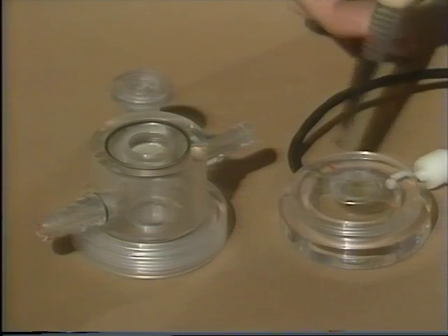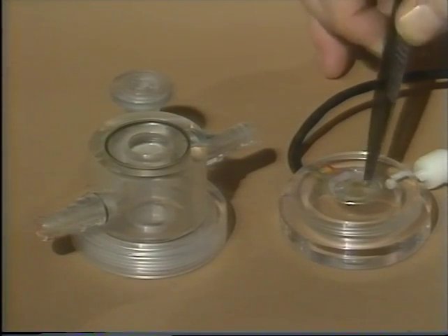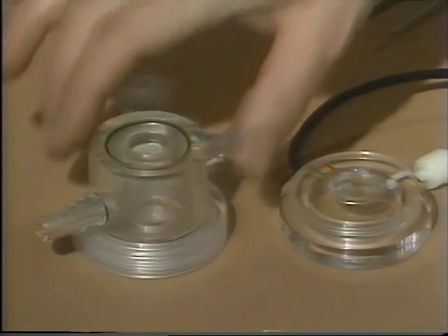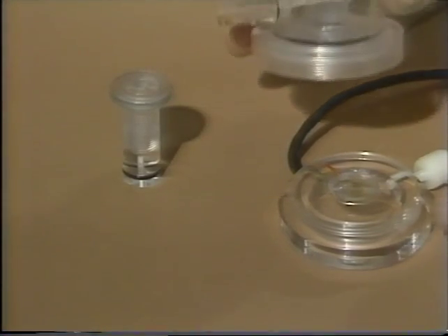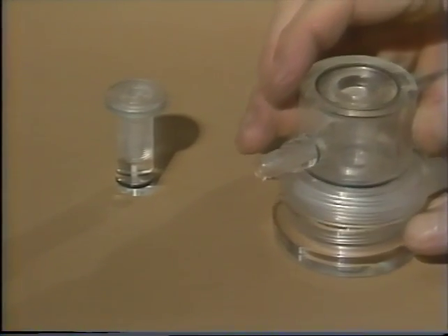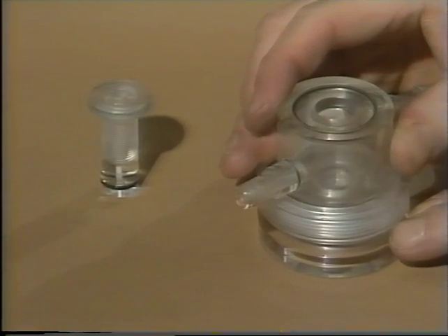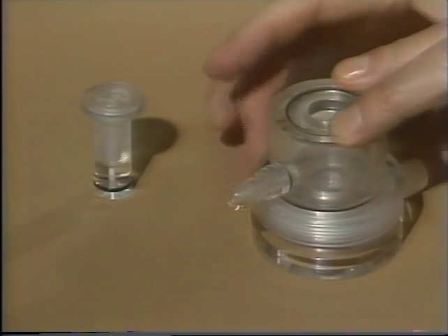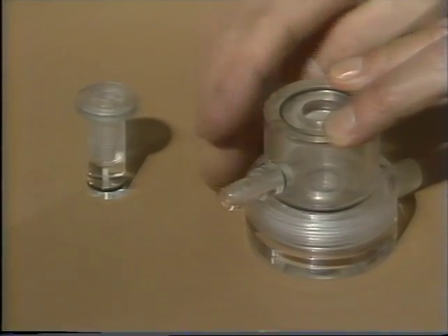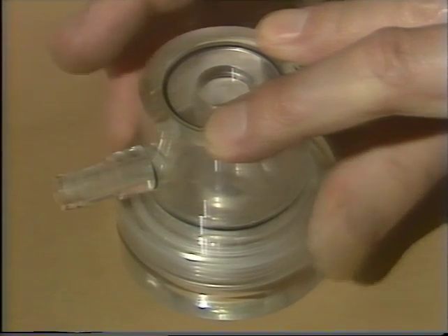A piece of lens tissue is put on to act as a spacer, and then a small piece of plastic film to keep the potassium chloride in place. The two pieces of metal are connected through the black lead to an electrical circuit, which applies a small voltage across them, and makes the platinum act as a cathode and the silver as an anode.